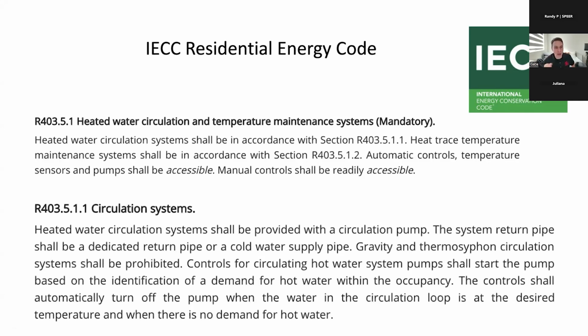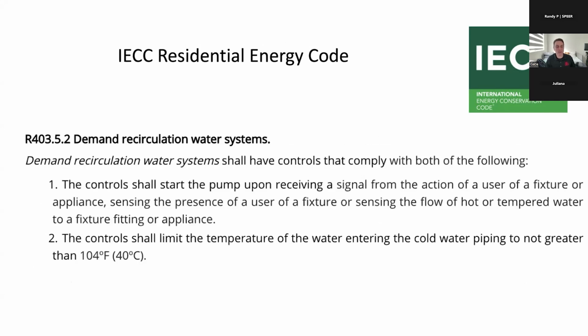Thanks. So IECC says that controls for circulating hot water systems shall start the pump based on the identification of a demand for hot water within the occupancy, and that the control shall automatically turn off the pump when the water in the circulation loop is at the desired temperature and there's no demand for hot water. Immediately after that, they have another section that further clarifies what demand circulation means, which is that it shall start the pump upon receiving a signal from the action of a user of a fixture or appliance, sensing the presence of a user of a fixture, or sensing the flow of hot or tempered water. So that's turning the pump on. Part one is turning the pump on, and then part two is turning the pump off based on sensing the temperature.